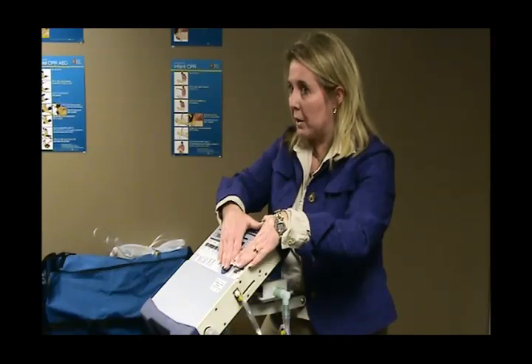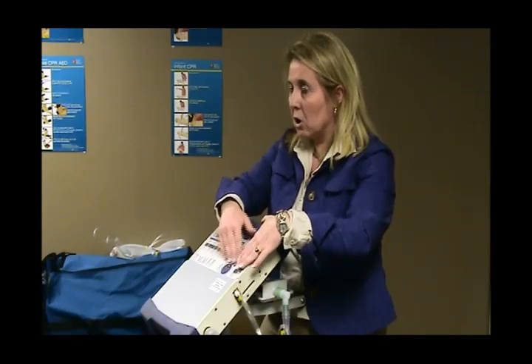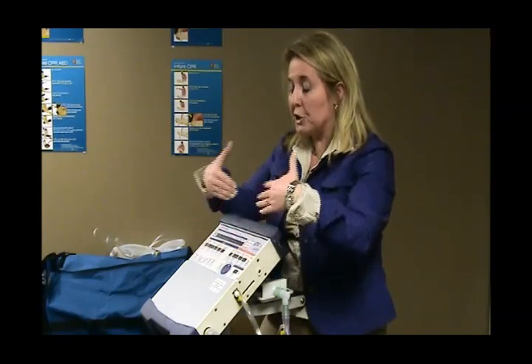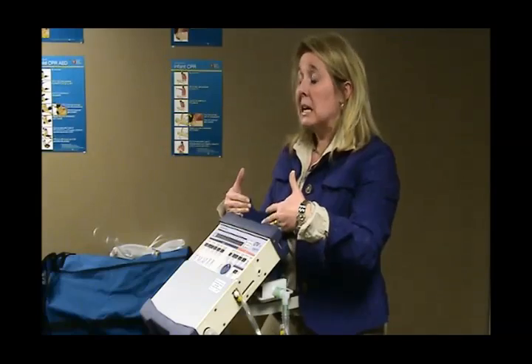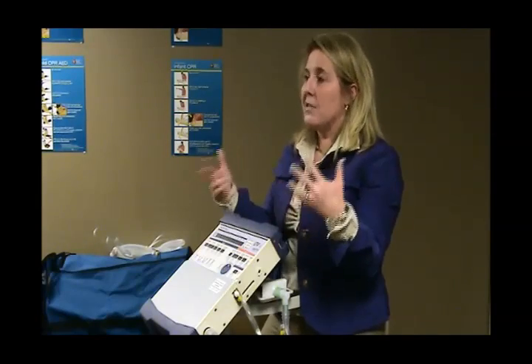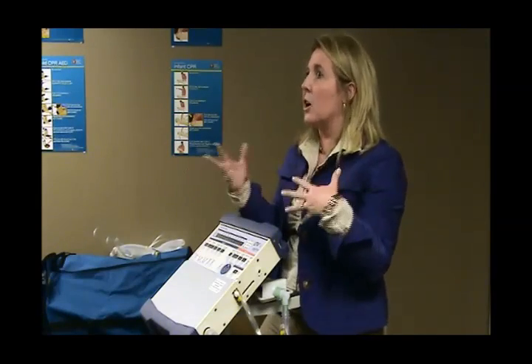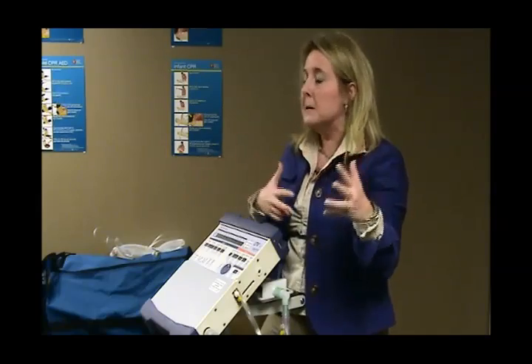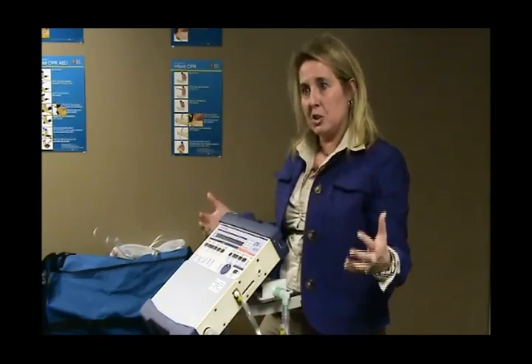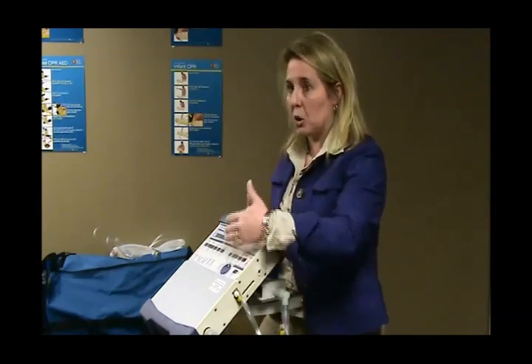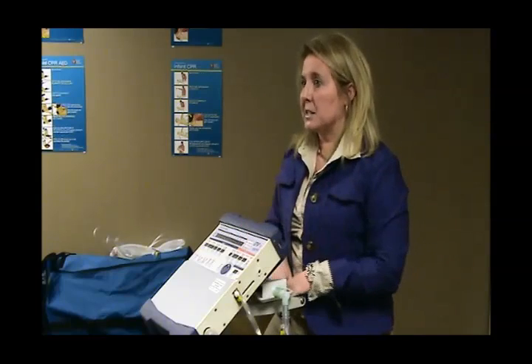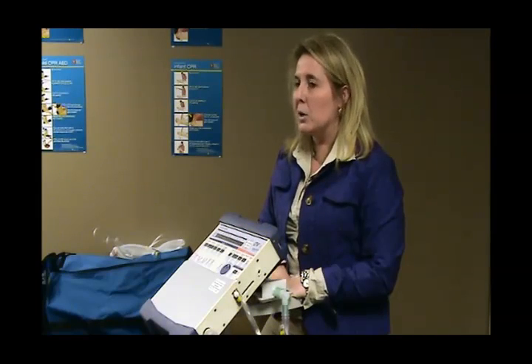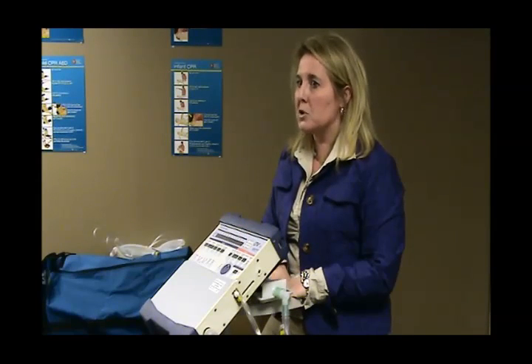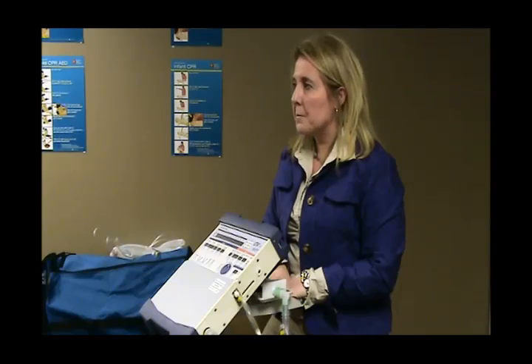You don't want to muck around too much with your alarms out here on the perimeter. Now there are some alarms in the back menus that will pop up on occasion, and the RTs definitely can go in and change those per patient, and they don't need orders for that. They can just do that. But to change something critical, like a safety alarm, like low minute volume, I wouldn't do that without a physician order. Okay?